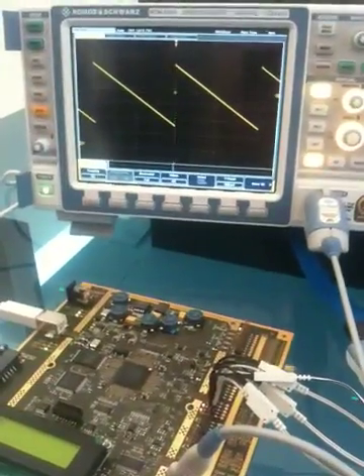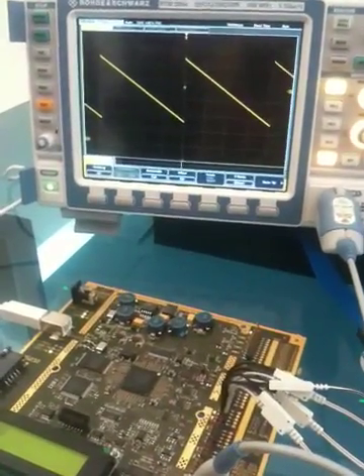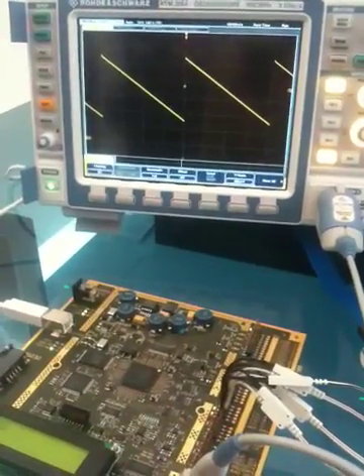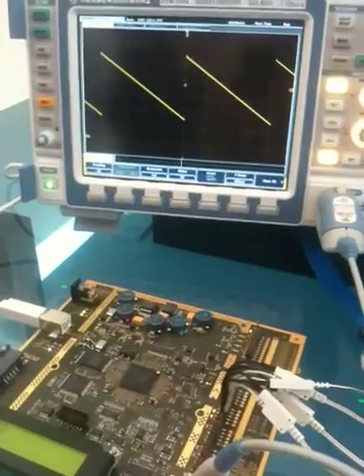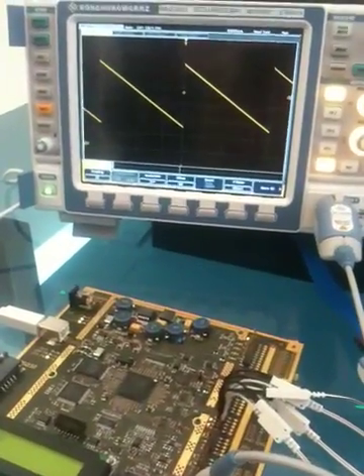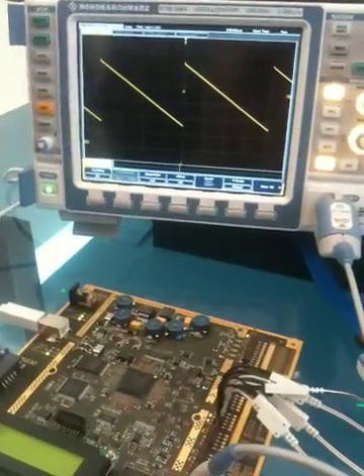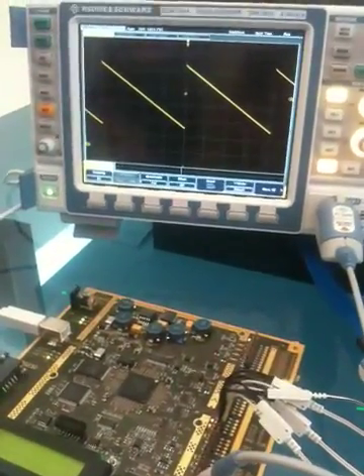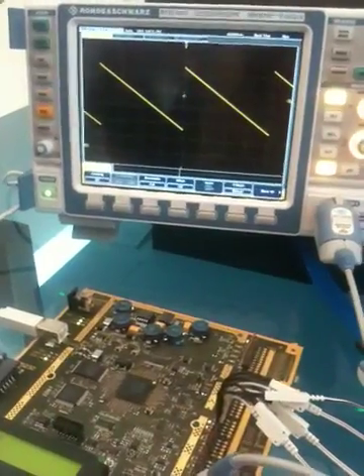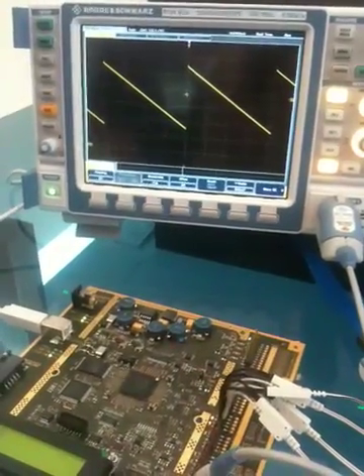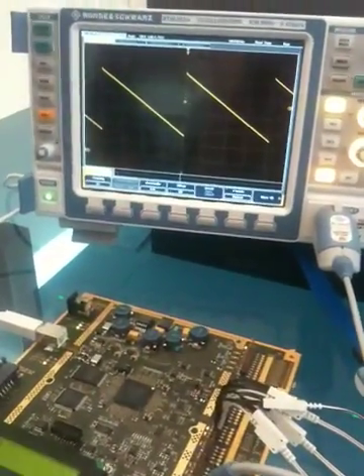One key upgrade in this new oscilloscope is adding an MSO option for digital channels, which I'm going to demonstrate now. All of the instruments are prepared for MSO, so customers don't need to decide in advance if they want MSO or not — they just get the option later on.